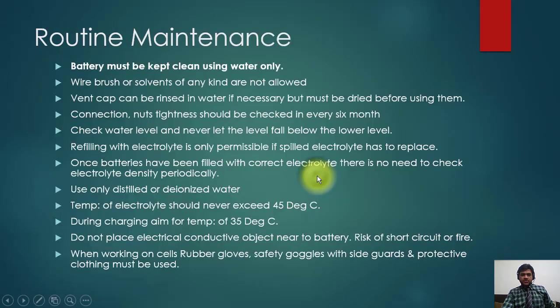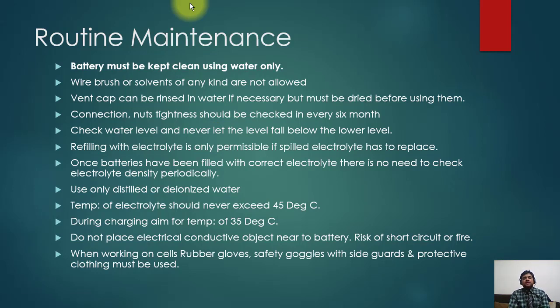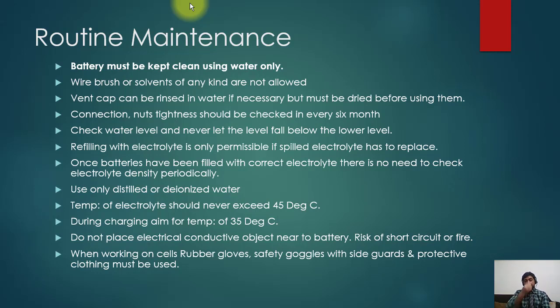For routine maintenance, batteries must be kept clean using water only. You should not use acid or any other solution, wire brush, or solvent of any kind — a wire brush can cause a short circuit. Vent caps can be rinsed in water if necessary but must be dried before using. If caps are clogged, gases cannot escape from the battery, pressure will build up inside, and it may chip or damage the battery cell.